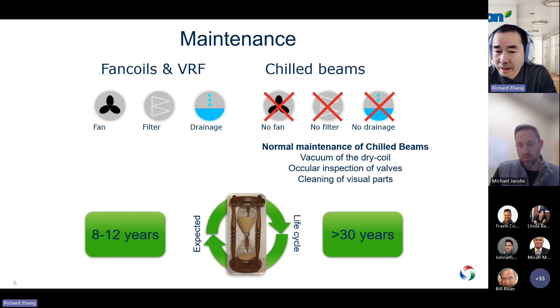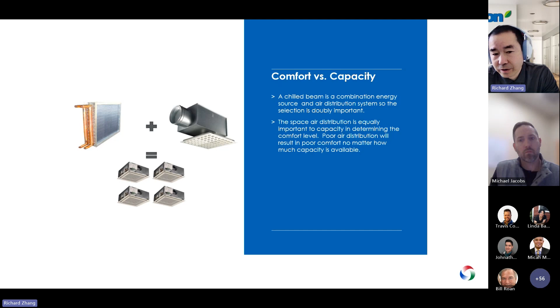So again, before we jump to the new generation of chill beam system via VAV chill beam, I just want to emphasize again: chill beam is not only the capacity equipment with the induction, but also the air distribution equipment. We are going to explain why a VAV box in front of a constant airflow chill beam will not work.